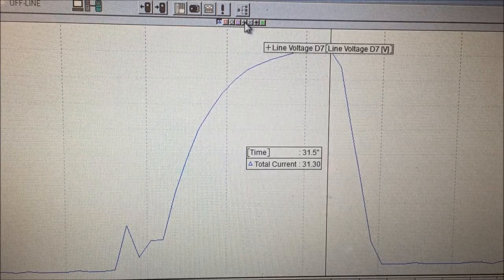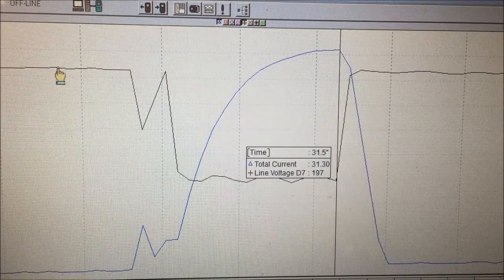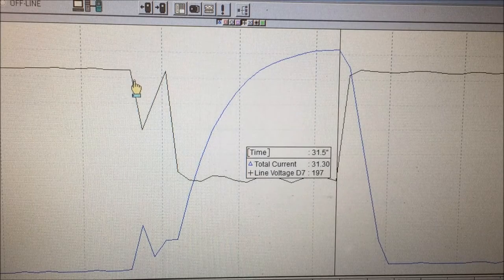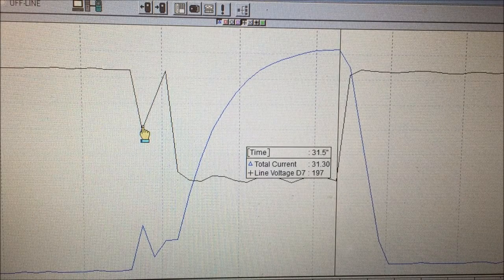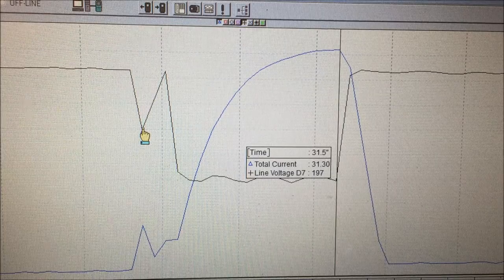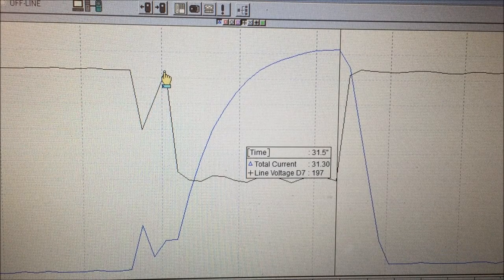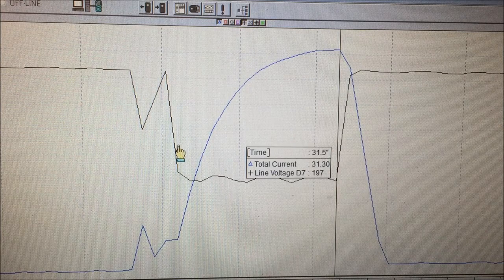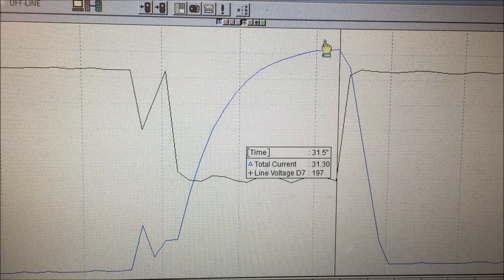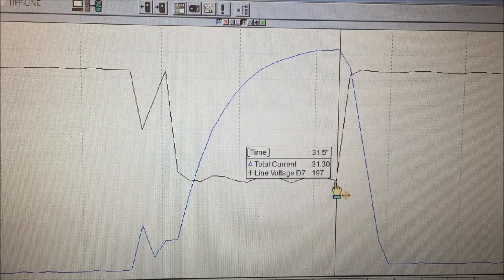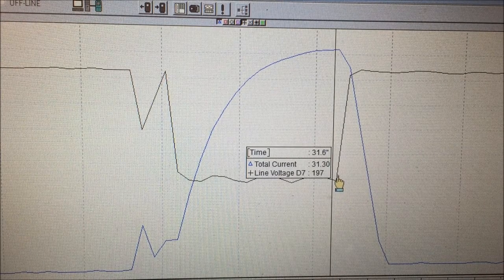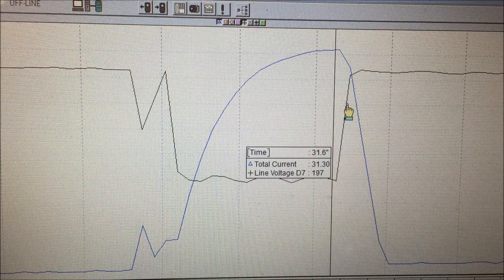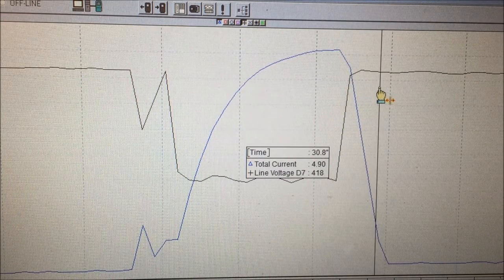What happened with the voltage during this? Here we can see that the voltage dropped a little bit when there was the short circuit. The current was cut off, the voltage came up probably just reactive current into the system then. And then it started feeding into the short circuit, the voltage drops down a little bit when the current goes up and the moment that the hardware fuse trips the voltage comes back online, the grid.